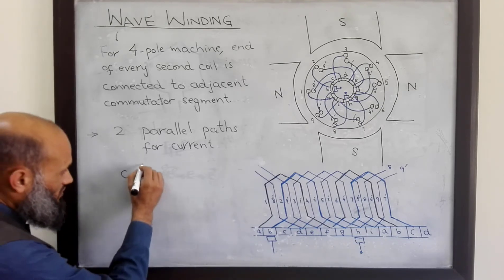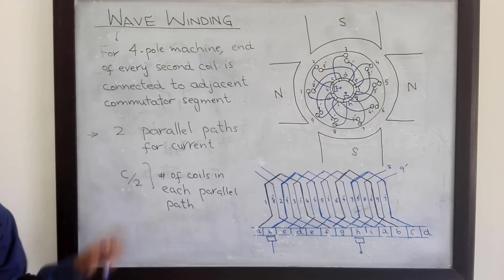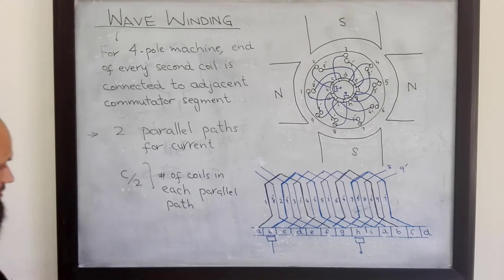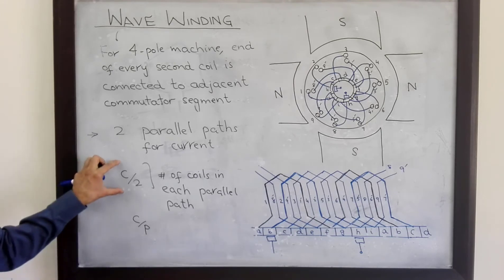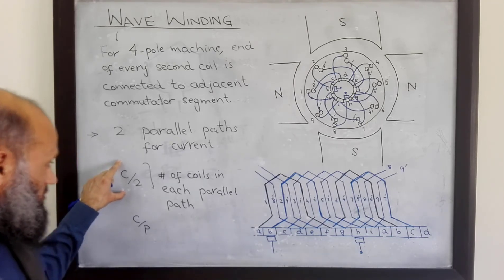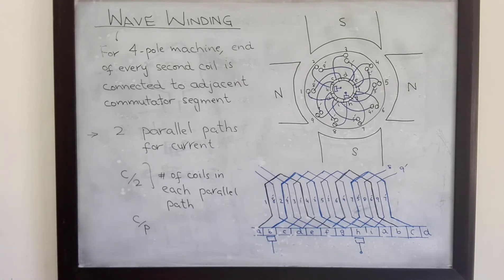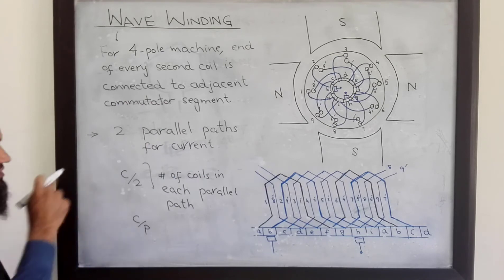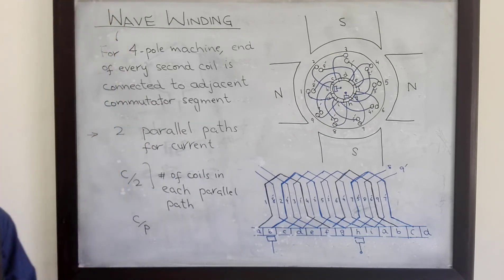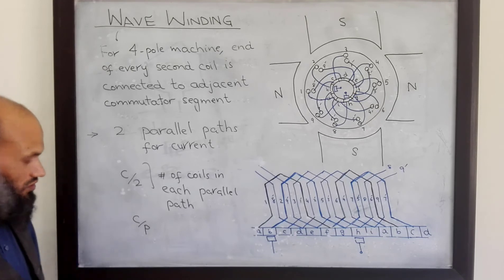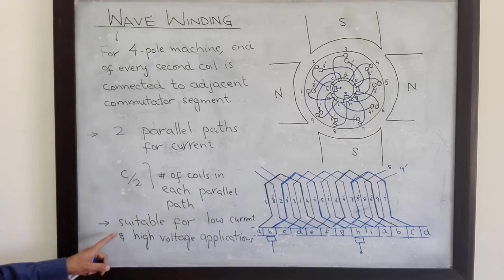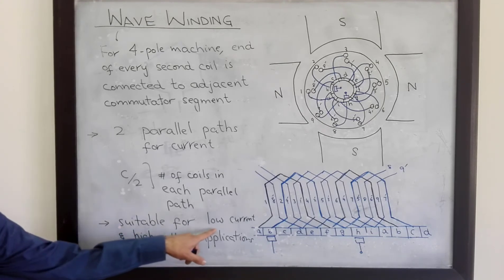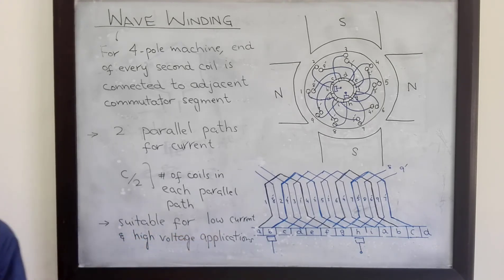Compared to the case of lap winding, where you had C divided by P coils in each parallel path, here you have more coils in each parallel path. More coils means the induced voltage available at the brushes will be larger. So wave-wound DC machines can handle more voltages — these are suitable for applications which have high voltages. Wave-wound DC machines are suitable for applications where you require low current and high voltages.